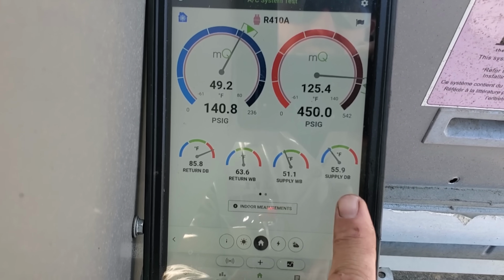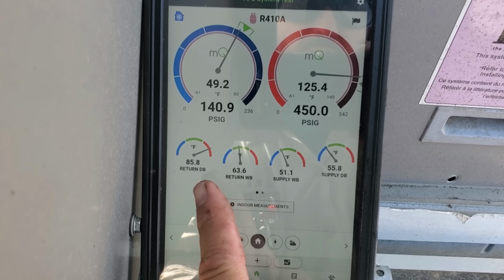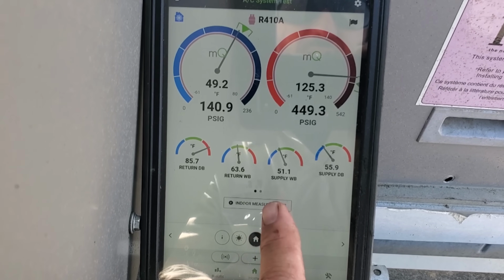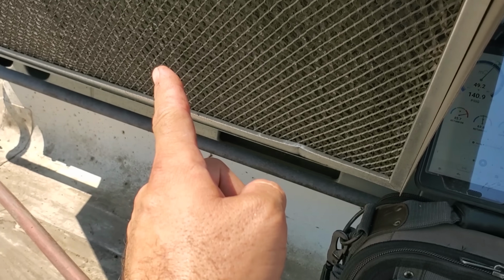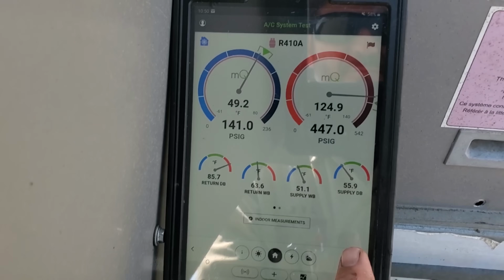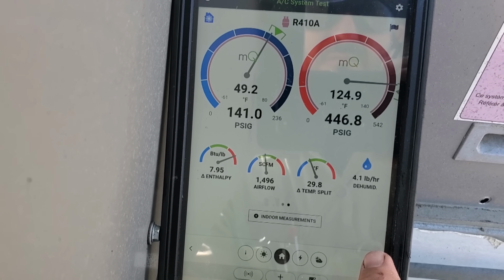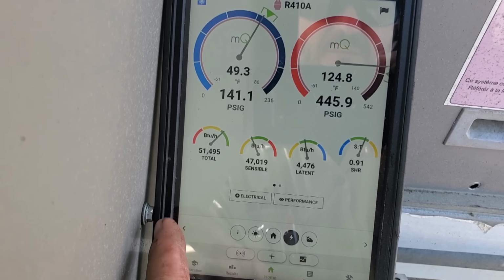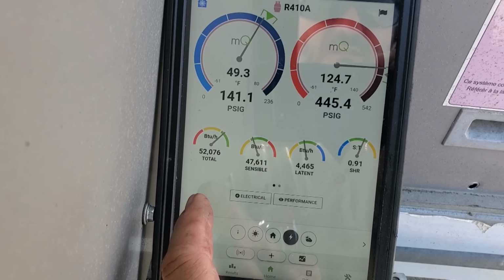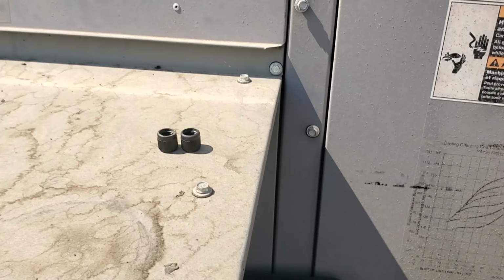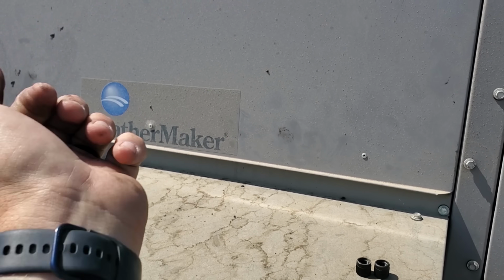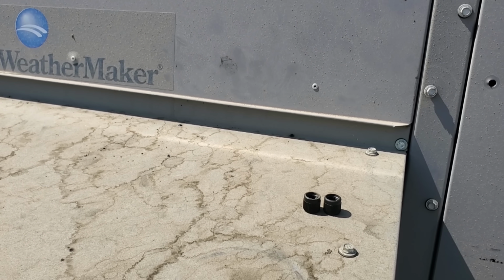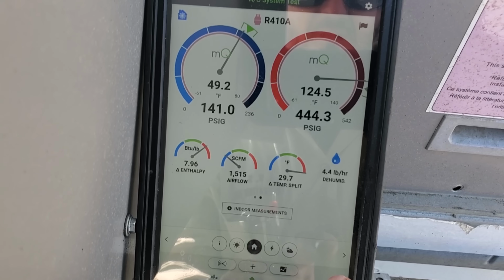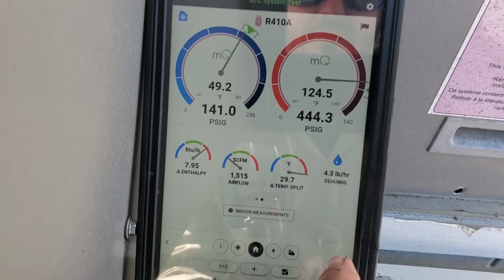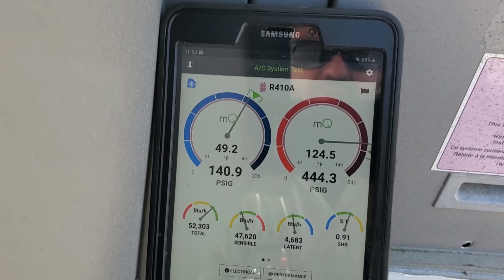Looking good. We have a high temperature split. It's really hot in that kitchen. And also I imagine we're probably pulling a little bit of outside air through the economizer damper too. Airflow looks to be low. And I think we have high return static because that panel is like sucking on. So I wouldn't be surprised if the return air grills are really dirty too. But look at that temp split too. That temp split's really high. So ductwork issues are pretty common.